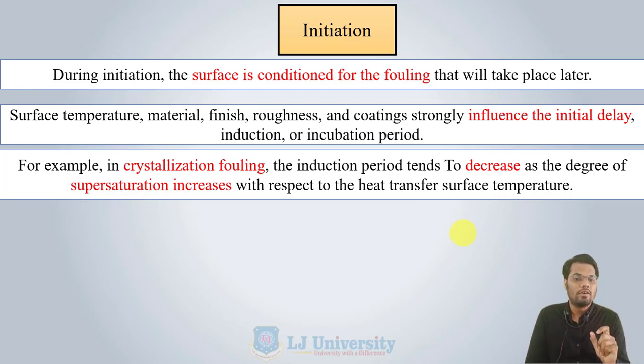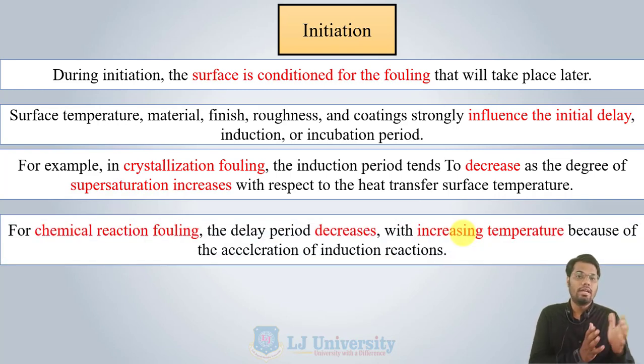In crystallization fouling, the induction period tends to decrease as the degree of supersaturation increases with respect to the heat transfer surface temperature. Same in chemical reaction fouling, the delay period decreases with increasing temperature because of the acceleration of the induction process. As the temperature goes high, the chemical reaction is rapid.